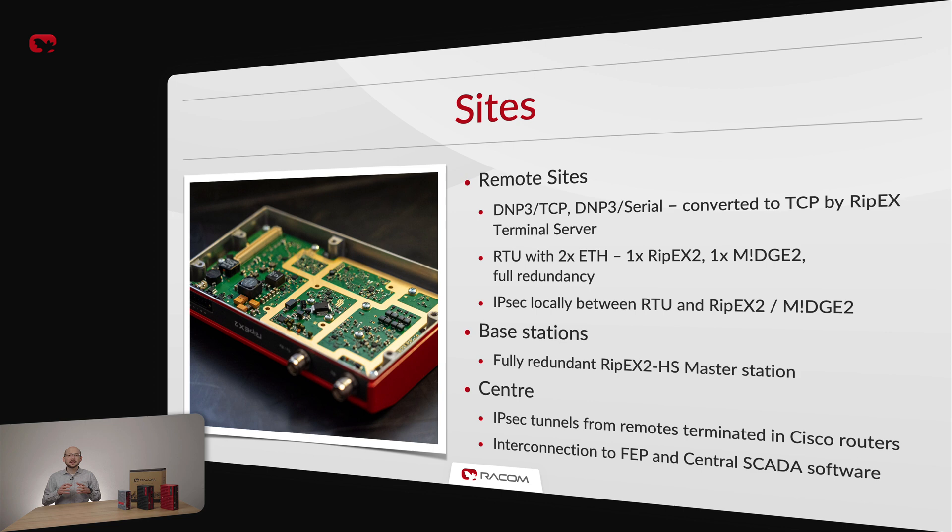RipEX2 is used as a primary channel in places where fiber or SHDSL are not available. M!DGE2 with two SIM cards is used as a backup channel on all sites. A solid network has been created, meeting and exceeding the highest possible requirements for reliability, security and speed. Since the network is fully TCP/IP, base-driven protocol is used on the radio channel. In order to provide maximum security, IPsec and AES are both used wherever possible, radio channel included. Since there are still legacy serial RTUs in the network, RipEX's built-in terminal server converting DNP3 serial to DNP3 TCP is particularly useful. All base stations are equipped with RipEX2 HS fully redundant master station, ensuring outage in any area is almost impossible.